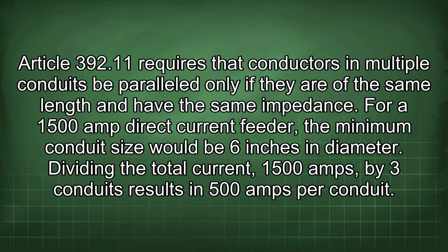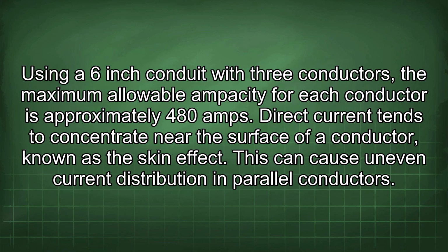Dividing the total current, 1500 amps, by 3 conduits results in 500 amps per conduit. Using a 6-inch conduit with 3 conductors, the maximum allowable ampacity for each conductor is approximately 480 amps.